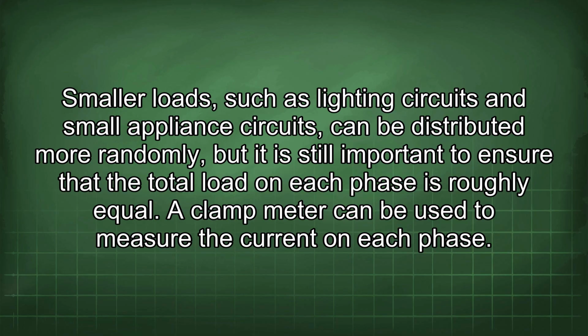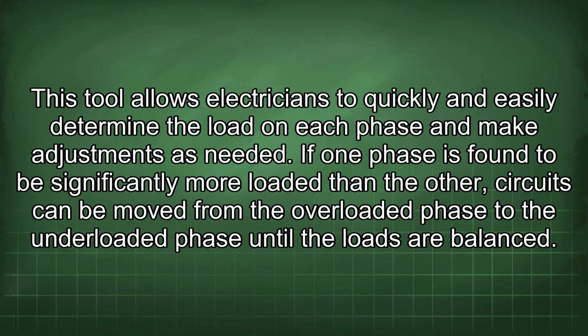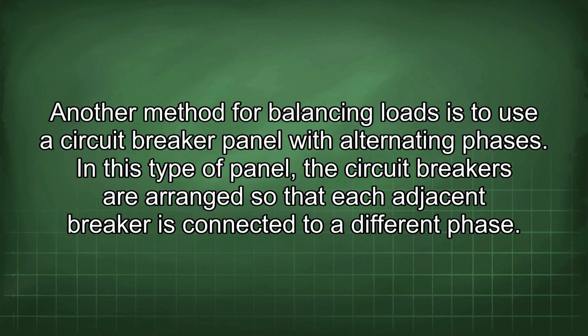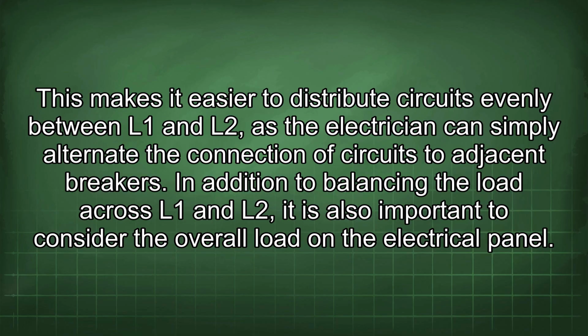A clamp meter can be used to measure the current on each phase. This tool allows electricians to quickly and easily determine the load on each phase and make adjustments as needed. If one phase is found to be significantly more loaded than the other, circuits can be moved from the overloaded phase to the underloaded phase until the loads are balanced. Another method for balancing loads is to use a circuit breaker panel with alternating phases. In this type of panel, the circuit breakers are arranged so that each adjacent breaker is connected to a different phase. This makes it easier to distribute circuits evenly between L1 and L2, as the electrician can simply alternate the connection of circuits to adjacent breakers.